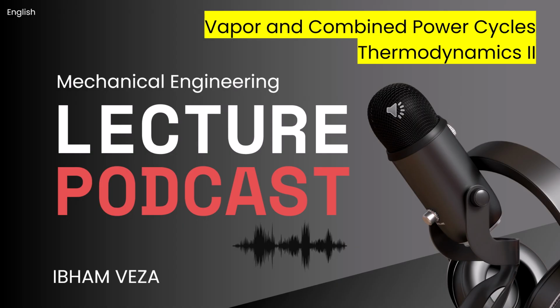Okay, direct mixing. Then there are closed feed water heaters. These work like a typical shell and tube heat exchanger. The steam and feed water don't mix. Heat just transfers across tubes. So indirect heating. Right. They can operate at different pressures and don't necessarily need that extra pump, but they're generally more complex and expensive. Most large power plants use a carefully designed combination of both open and closed heaters to get the best results. So putting it all together, regeneration boosts efficiency significantly.